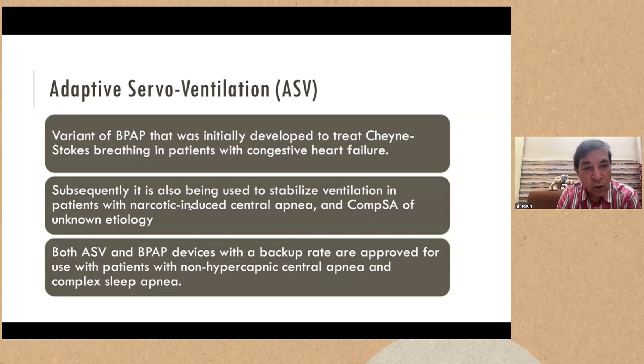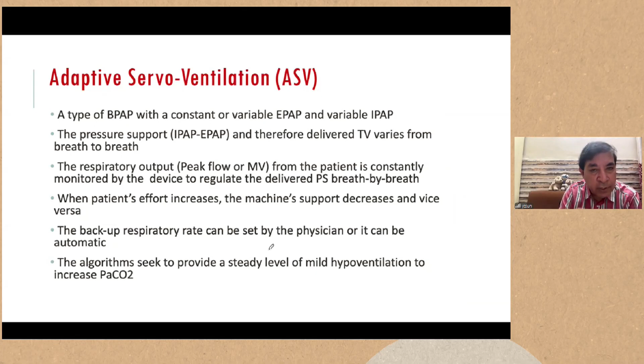So it's a type of bi-level device, but the difference is that it changes the pressure support on a breath by breath basis. Because in periodic breathing, there is a crescendo-decrescendo type of breathing. As a result, the pressure support, as you can see here, changes according to the periodicity. If the patient is making more effort, the machine will give less pressure support. If the patient is making less effort, the machine gives more, and with this the machine stabilizes the breathing.